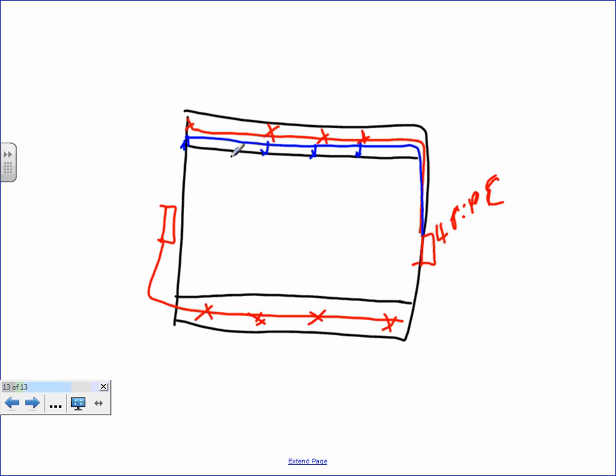Matt, space-wise, NFPA would say 30 by 30, you put one smoke detector at the top, but at the bottom, do we cut the distance by half, or do we put them on the raised floor? It's the same. You're starting at 30 by 30, every 30 feet on center. Yep. But depending on the air movement is when you have to reduce your spacing.